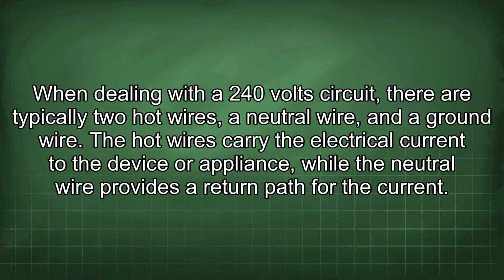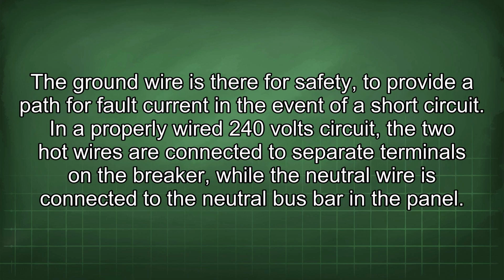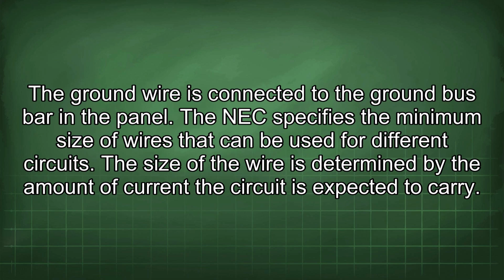When dealing with a 240-volt circuit, there are typically 2 hot wires, a neutral wire, and the ground wire. The hot wires carry the electrical current to the device or appliance, while the neutral wire provides a return path for the current. The ground wire is there for safety to provide a path for fault current in the event of a short circuit. In a properly wired 240-volt circuit, the 2 hot wires are connected to separate terminals on the breaker, while the neutral wire is connected to the neutral bus bar in the panel. The ground wire is connected to the ground bus bar in the panel.